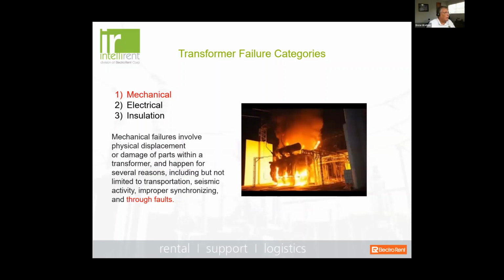Now, basically, when we talk about transformer failures, there are three particular categories. You have mechanical, you have electrical, and you have insulation failures. Let's talk first about mechanical failures, because these involve physical displacement or damage of parts within the transformer that can happen for a number of different reasons. And of course, when we think of a mechanical failure, we think of moving a transformer from one location to another, or it's coming from the factory and going on a rail car. And rail cars have a tendency to bump and cause a lot of vibration when they're coupling and decoupling.